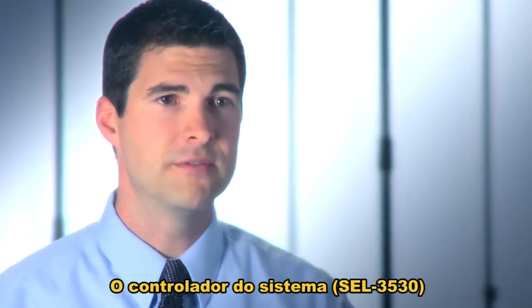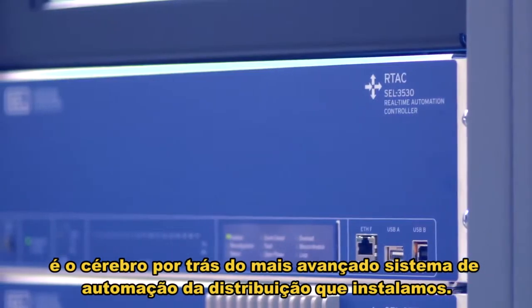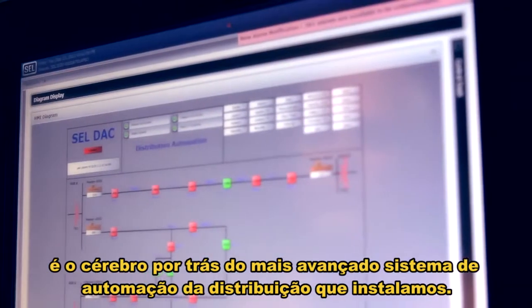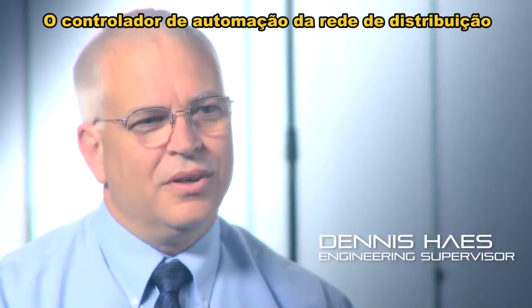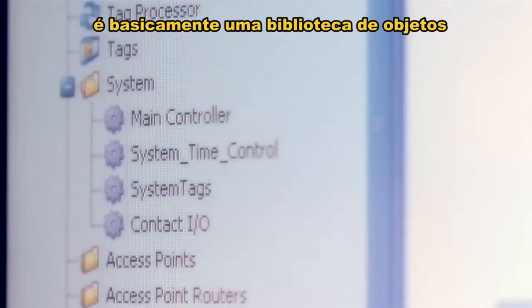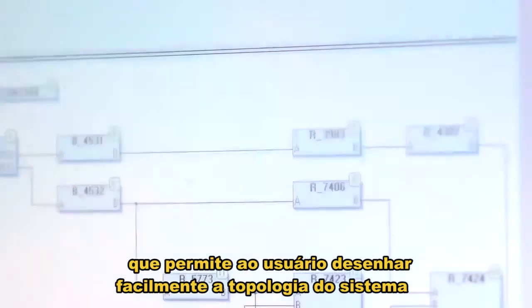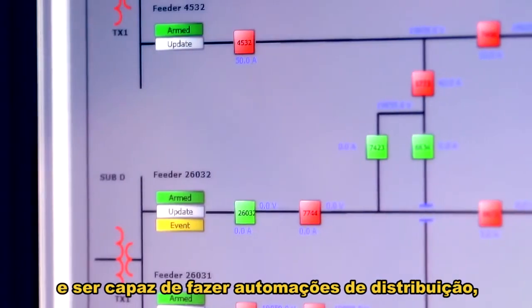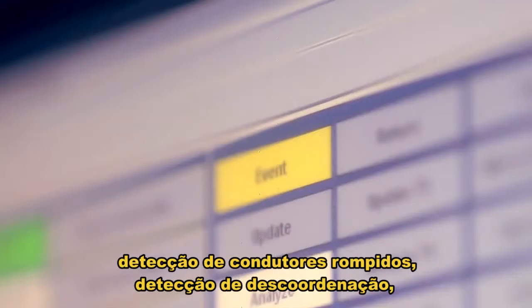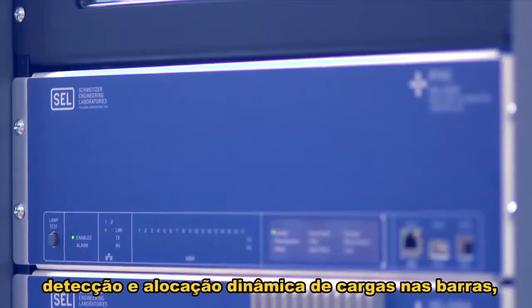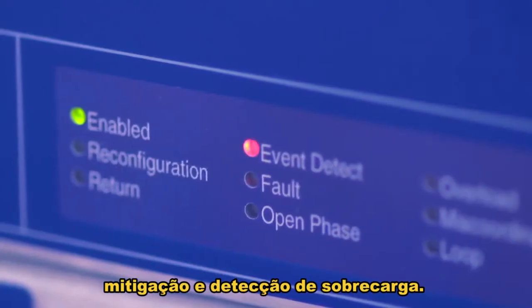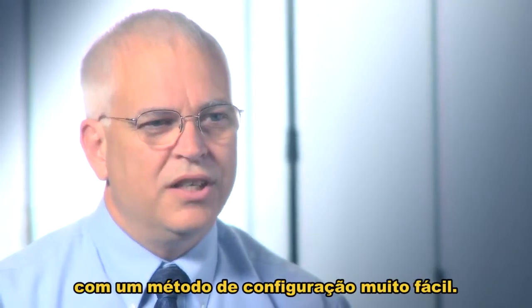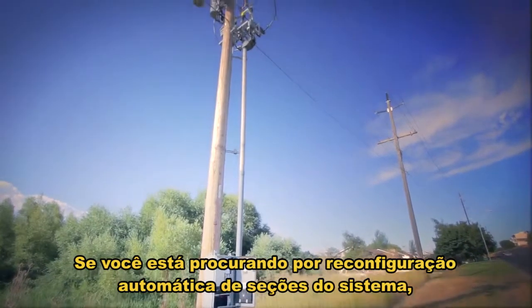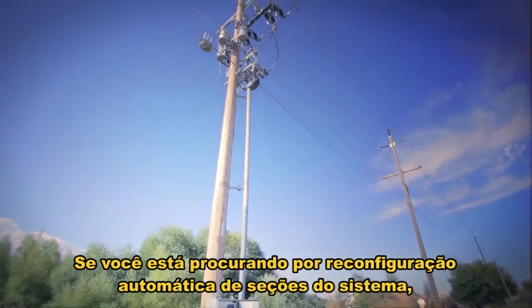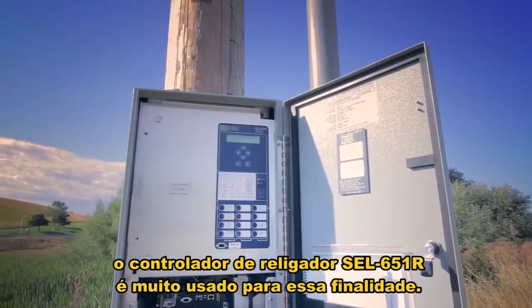The DA controller from SEL is the brains behind the most advanced DA systems that we've been installing. The distribution automation controller is basically a library of objects that allow a user to easily connect the topology of their system and be able to do distribution automation such as fault location, broken jumper detection, miscoordination detection. We have dynamic bus load allocations, loss of source mitigation, overload detection, a variety of different functions in a very easy to configure method.